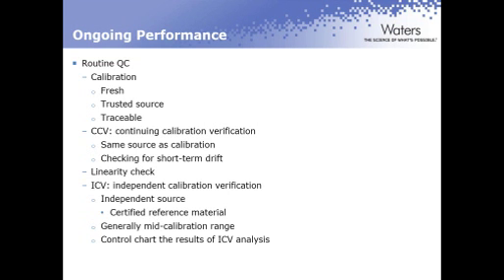Okay, also, do continuing calibration verifications. As your run goes on, make sure that the instrument isn't drifting on you. We talked about the variable of environmental conditions. So your continuing calibration, or a CCV, should be made from the same source as your calibration, so that the variable of an independent source doesn't come into play, but it's purely to make sure that your method isn't drifting over time. So that helps check for the short-term drift.